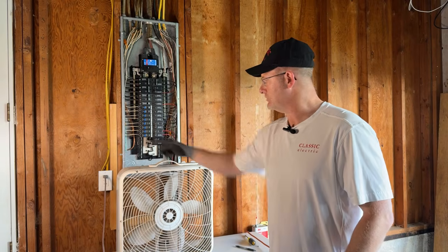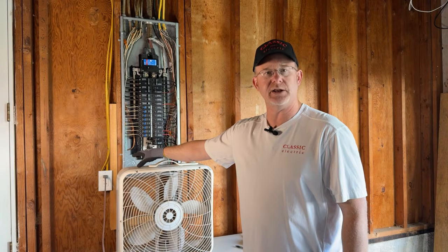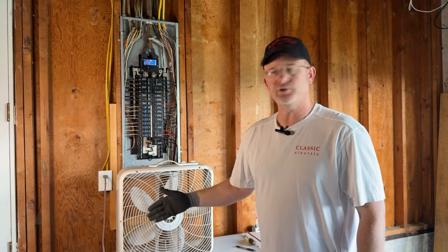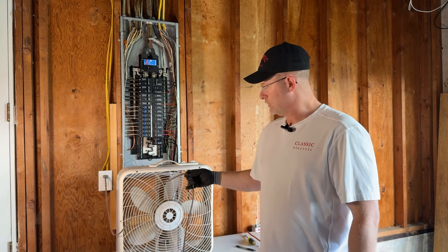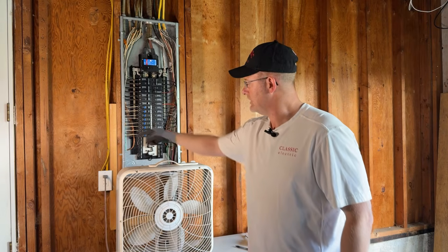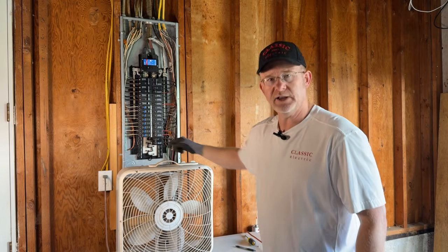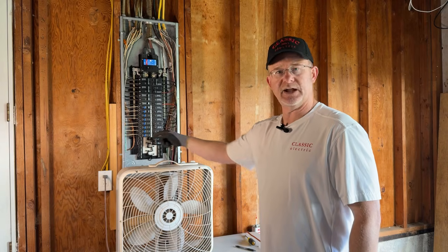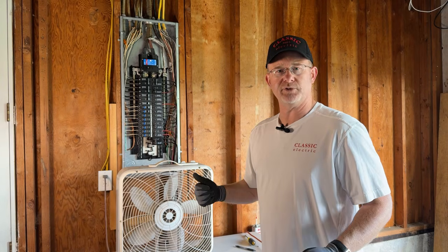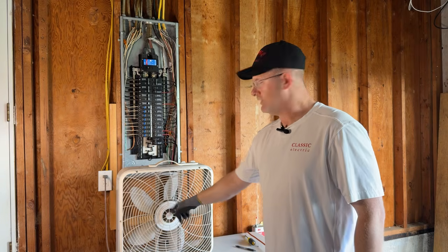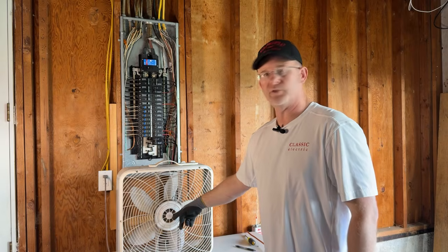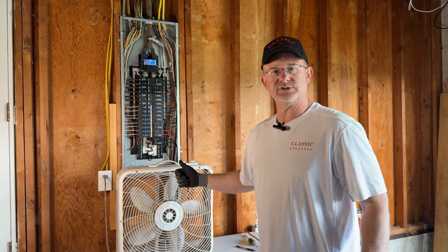And so what's happening is this thing has such a sensitive element in it because it's to protect people. Well, what is it doing? Well, imagine if this cord had a nick in it and it was a little bit wet. This thing is sensing the amount of current going in and out of it. And if it isn't exactly the same going out as it is coming back, it assumes it's going to a person and then it trips. That's what it's doing. But what's happening is the motor is breaking down and that thing can't tell whether it's me, the person, or the motor that's breaking down, so it shuts off.